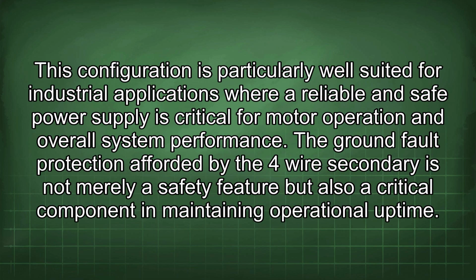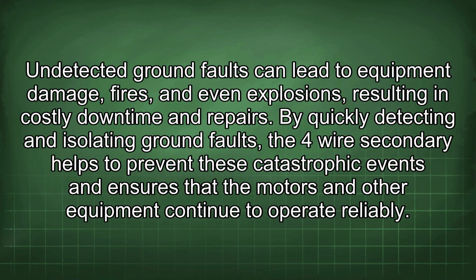This configuration is particularly well suited for industrial applications where reliable and safe power supply is critical for motor operation and overall system performance. The ground fault protection afforded by the 4-wire secondary is not merely a safety feature, but also a critical component to maintaining operational uptime. Undetected ground faults can lead to equipment damage, fires, and even explosions, resulting in costly downtime and repairs.